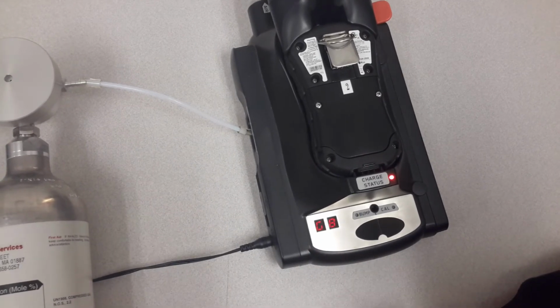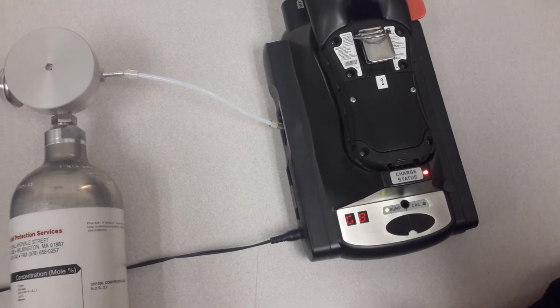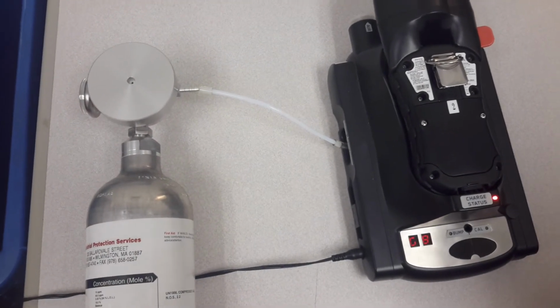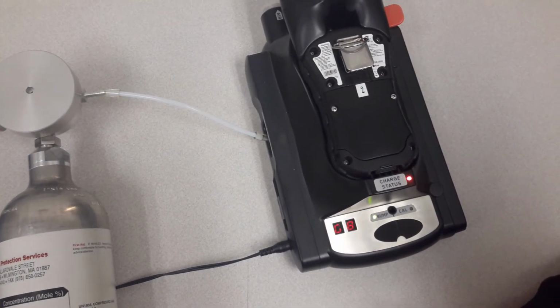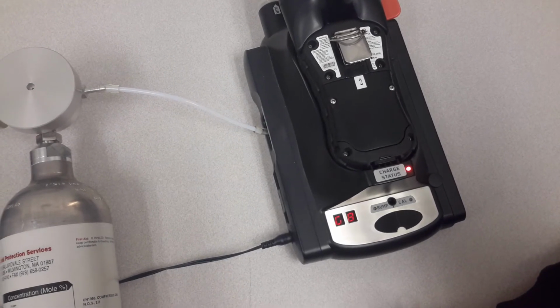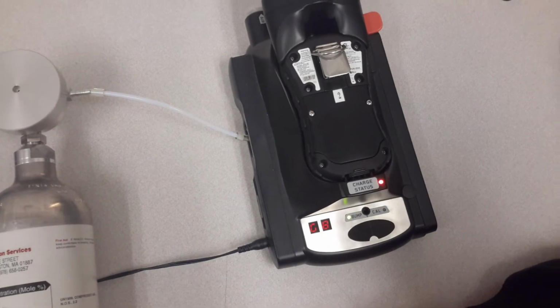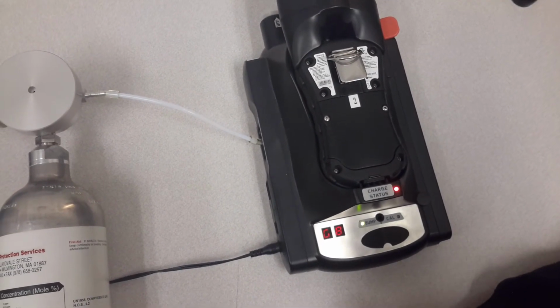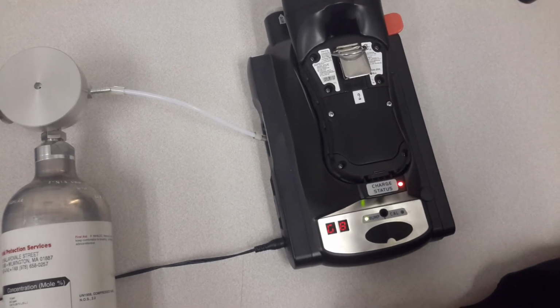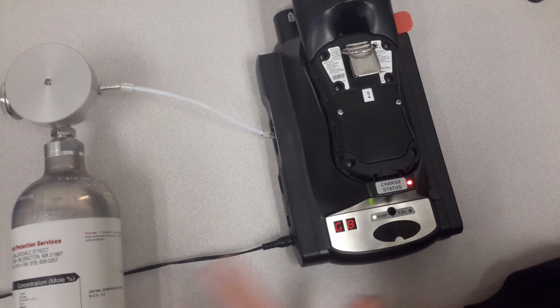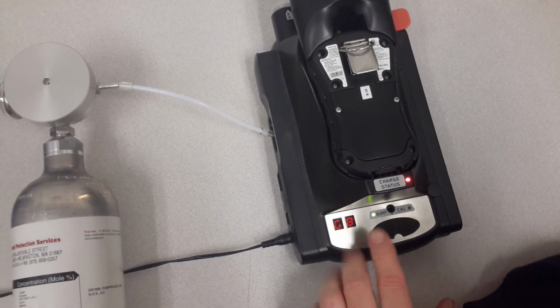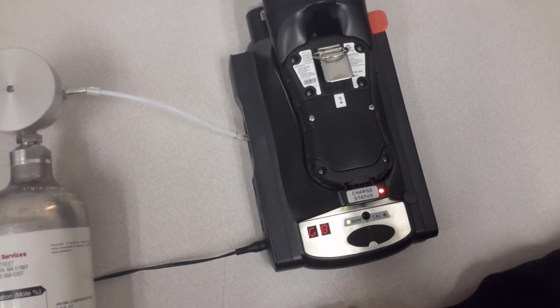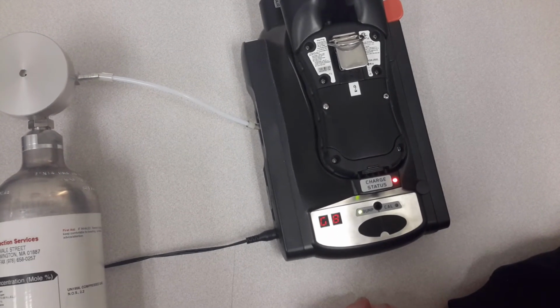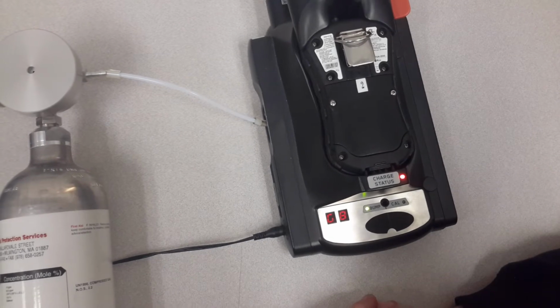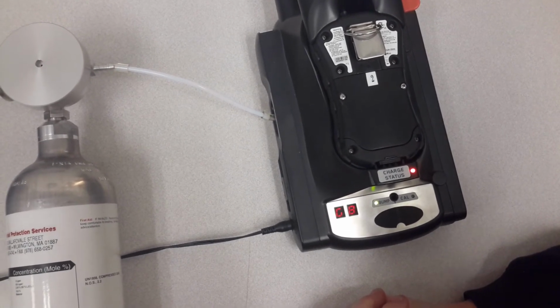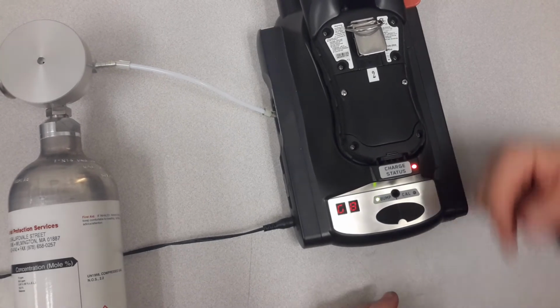When you do the test, you'll start to smell the different kinds of gases in the room air. So to help save time on the video, after we pressed that bump test there and it was flashing and calibrating, the unit did sound with one beep, and then, as you just heard, you heard 3 beeps, and that signifies that the bump test is complete. So that's all you have to do here.